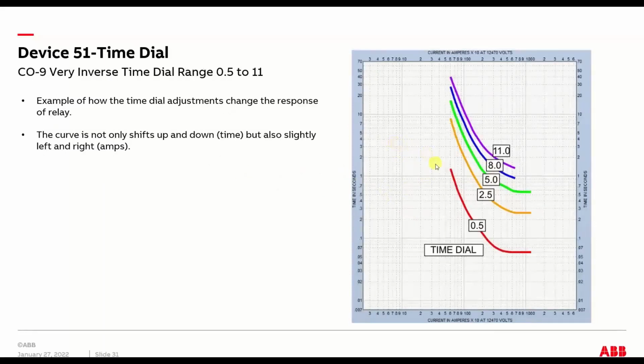Here's an example of the time dial adjustment. This is a CO9, a very inverse curve, and here are the different time dial settings. It's really meant to illustrate that in relays, it's not a true up and down change in time. It's more of a slope to the left and right. So as you increase the time dial, the slope is moving up, but it's also moving a little bit to the right in terms of amps. So the way the curve looks kind of changes, and that's a little bit different than the way low voltage breakers with electronic trips work.